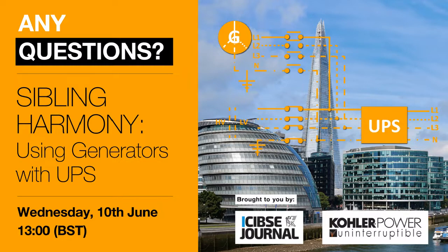Okay, thanks for that. This one's from Daniel. Daniel asks, what as a percentage would you, as a manufacturer, accept as a maximum step load? I think you spoke about that on around slide 12. Peter, can you take over? You've got a lot more experience on that. Yeah, I can. Engines vary in load acceptance, depending on the size of the generator and the type of engine used. Anything from 50 to 75% load impact is normal, but it's not one figure for everything. They do vary depending on the kVA of the generator and the make of the engine. But 50 to 75% is the sort of ballpark where they generally are. Okay, that's clear. Thank you for that, Peter.